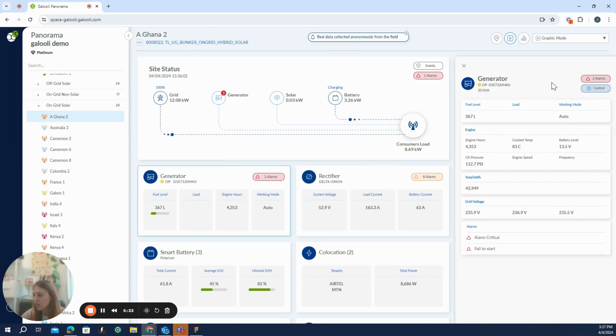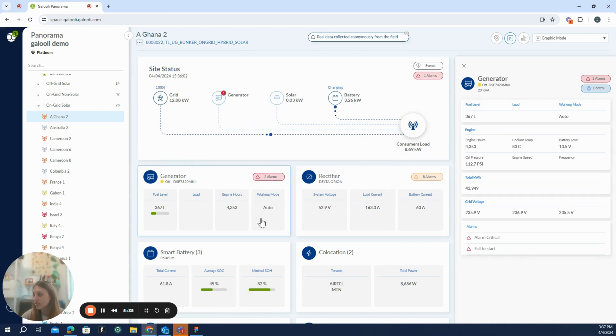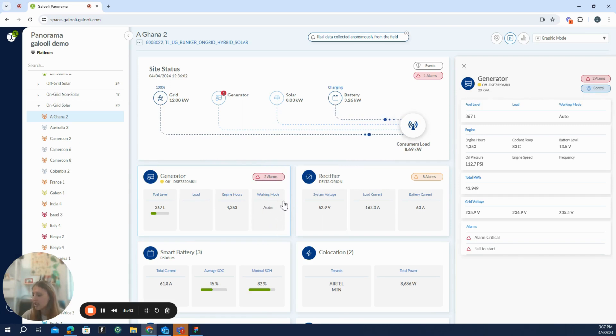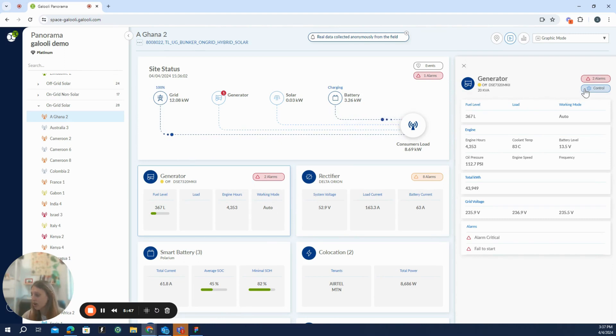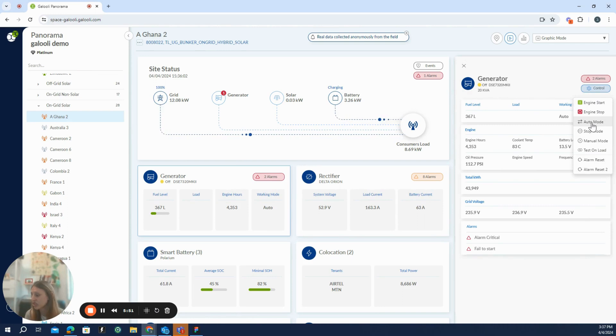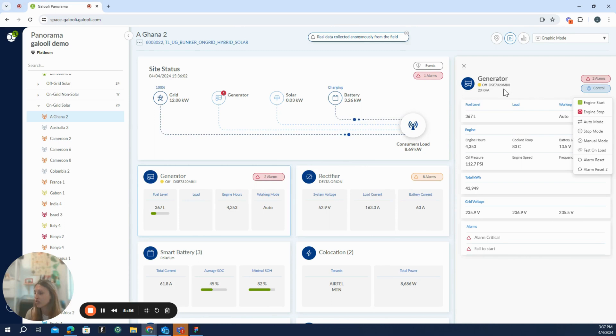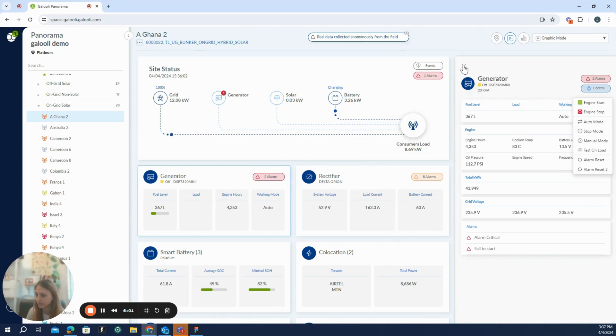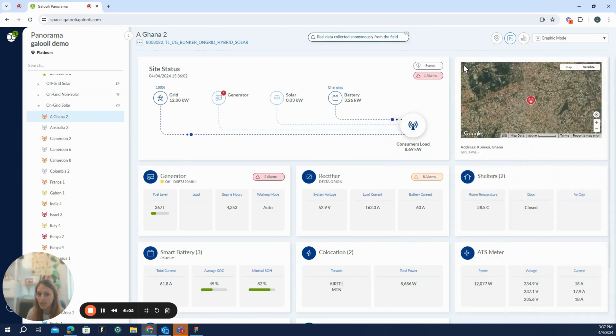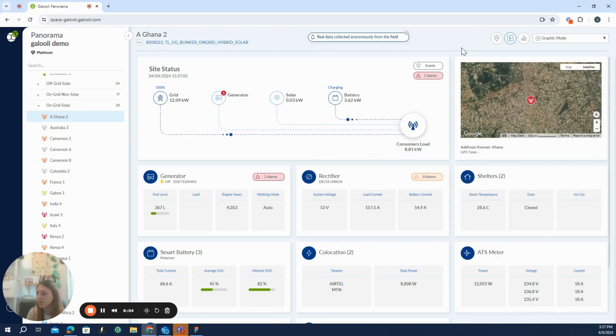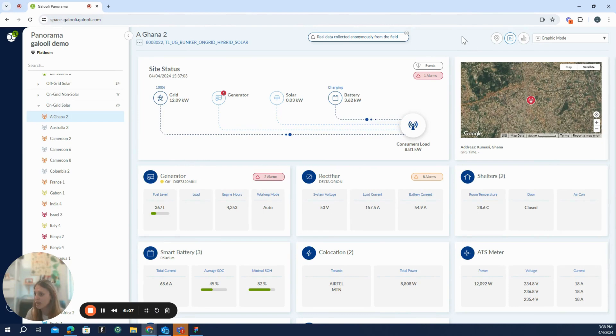For example, if a client has a situation on site where the generator is running for no reason and is in manual mode, not auto as stated here, instead of just sending someone to the site, he can also log in, go to this menu and just send the command to switch the generator mode to auto. So this is very useful because you're not only viewing what is going on, you can also affect the site itself.